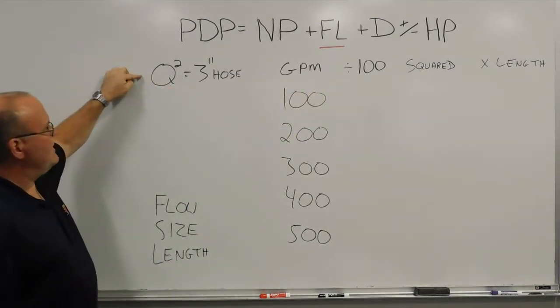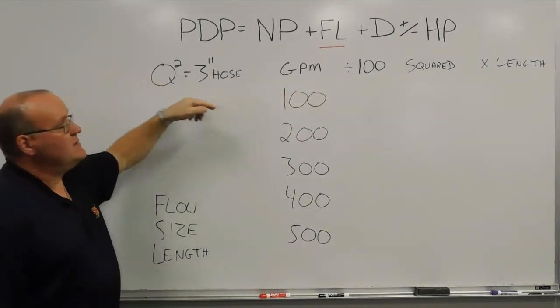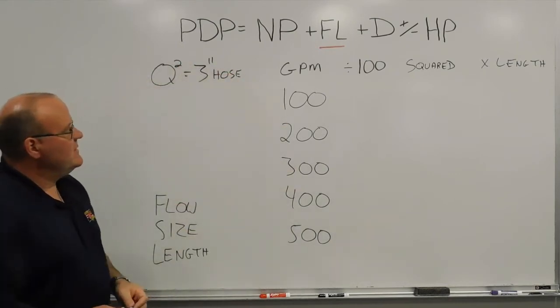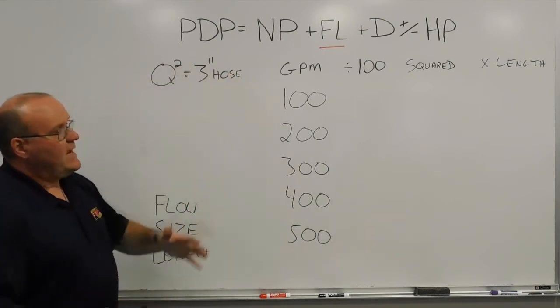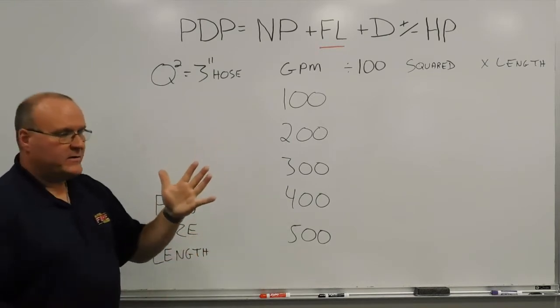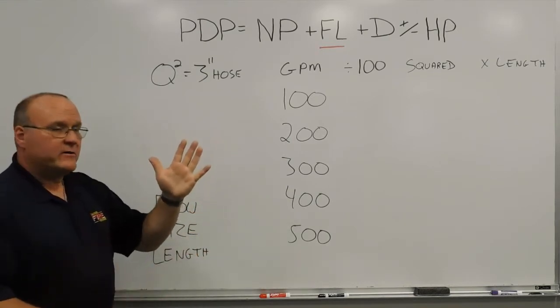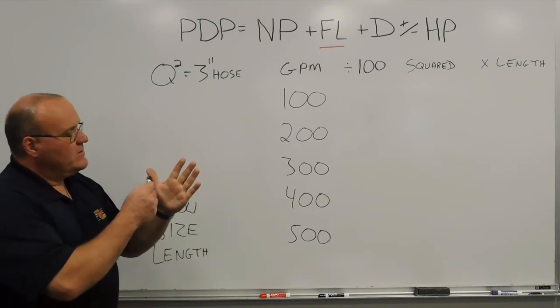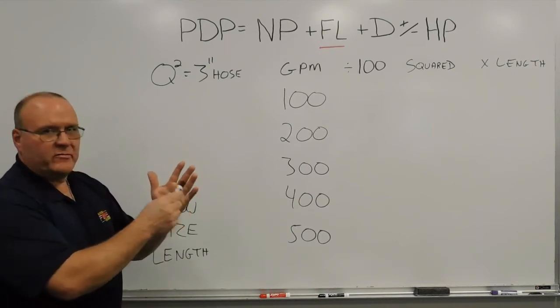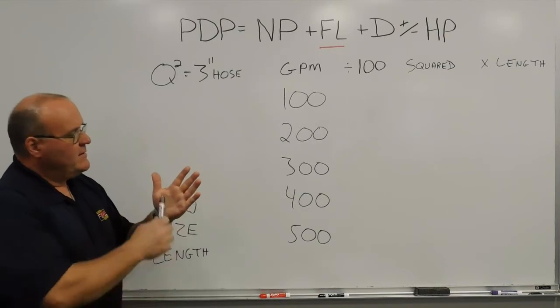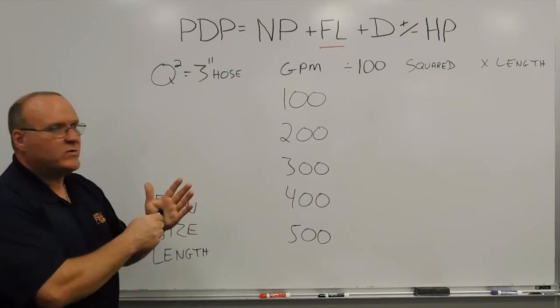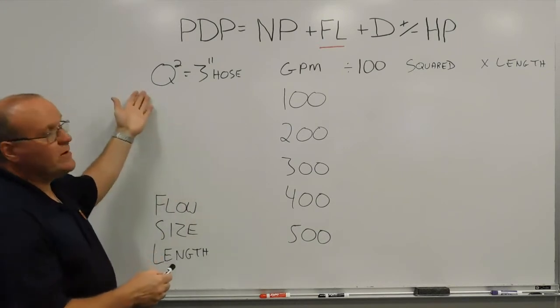Q-squared is basically the gallons per minute squared after it's been divided by 100. This makes it a hand method — useful at 2 o'clock in the morning. You have your hand here, your hillbilly calculator, if you will. 100, 200, 300, 400, and 500 from left to right, thumb to pinky. And then on the palm, you visualize a multiplication symbol. That gives you your squared.